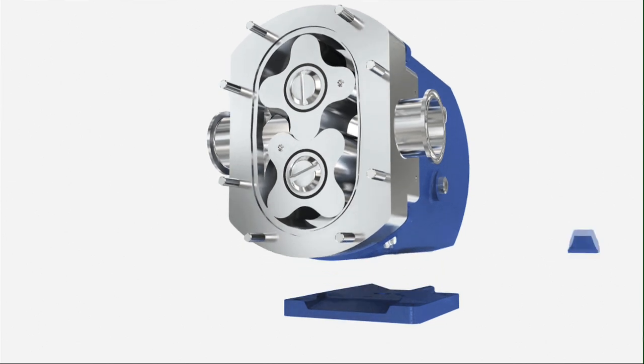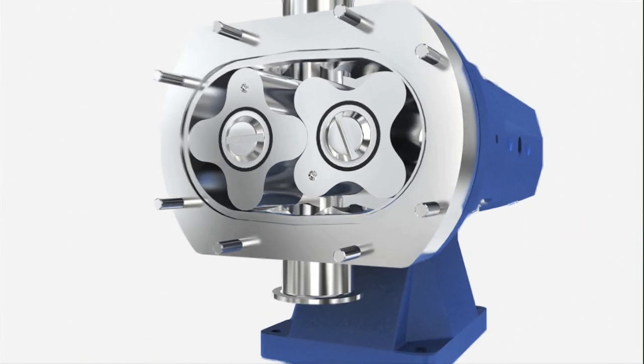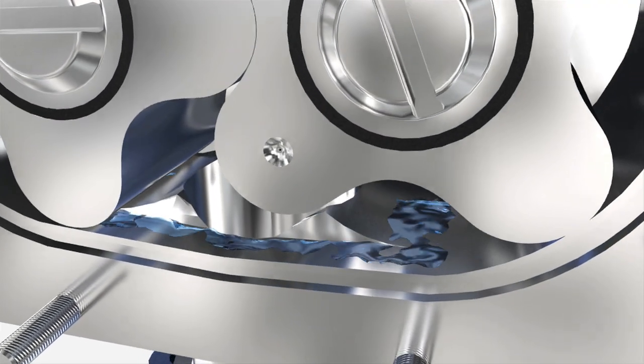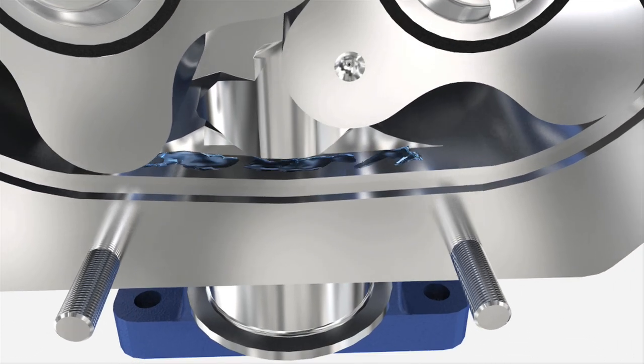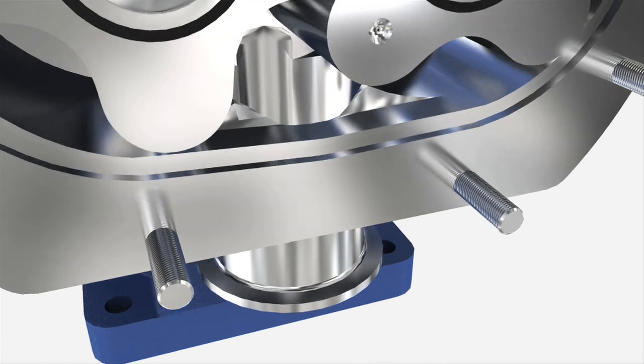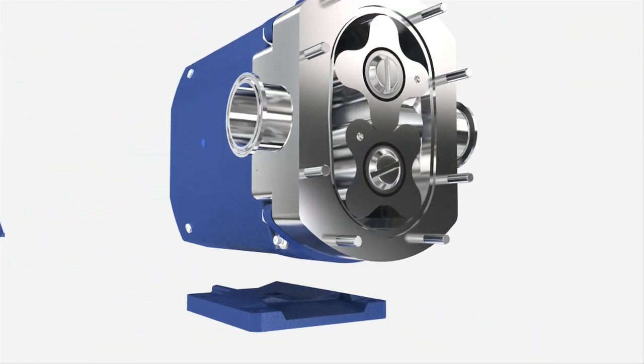Universal mounting gives complete installation flexibility throughout the plant. By setting back the cusps and incorporating a three-degree fall angle, the pump can be completely drained while retaining pump efficiency. This provides increased product recovery and ensures the elimination of any condensate trap during sterilization.